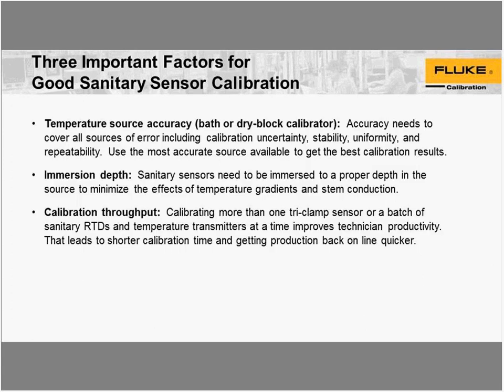In the factories that we've visited, there are hundreds or thousands of these sensors installed throughout the different processes. This is where it's important to measure temperature. So if you're calibrating these sensors, we want to go over three important factors for making a good calibration with these tri-clamp sensors.